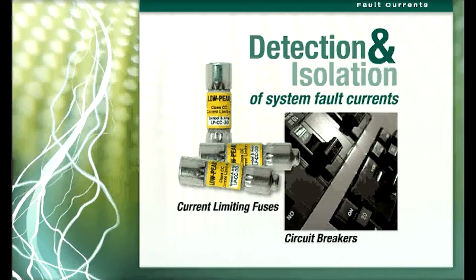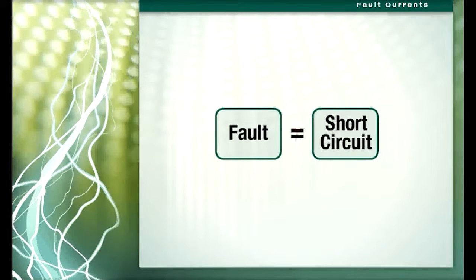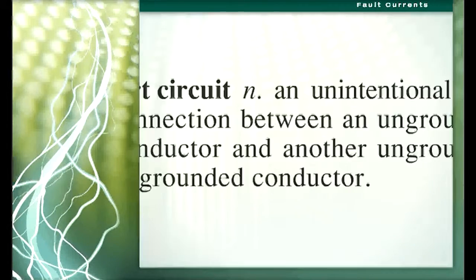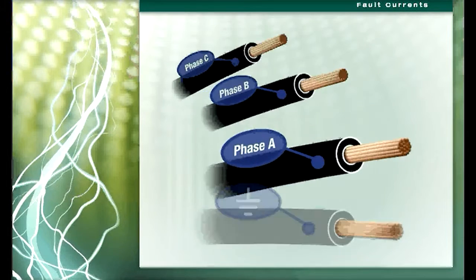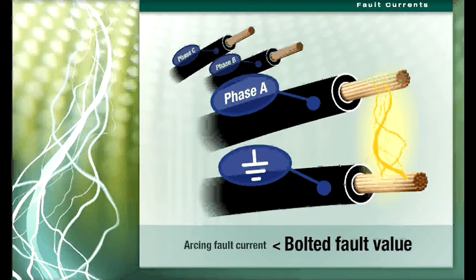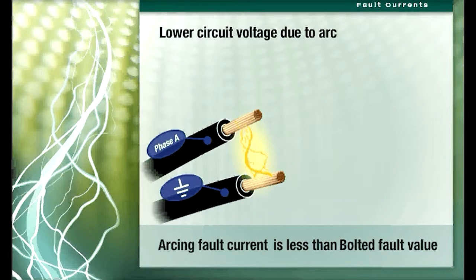Detection and isolation of system fault currents is generally achieved with circuit breakers or current limiting fuses. The term fault is often used interchangeably with short circuit, while a short circuit is a fault, not all faults are short circuits. In general, a short circuit is an unintentional hard connection between an ungrounded conductor and another ungrounded conductor or grounded conductor. Current will also flow between conductors of differing potential through an arc. The arcing fault can occur between phases and between phase and ground, and arcing fault current is considerably less than the bolted fault value.